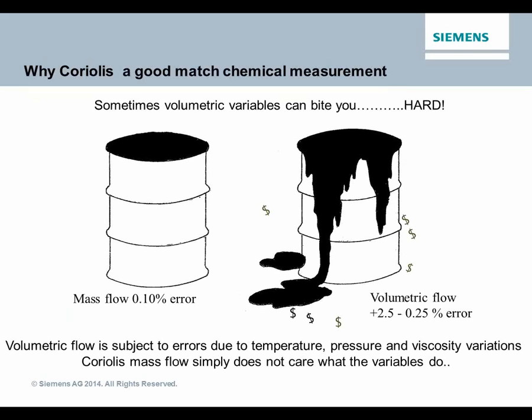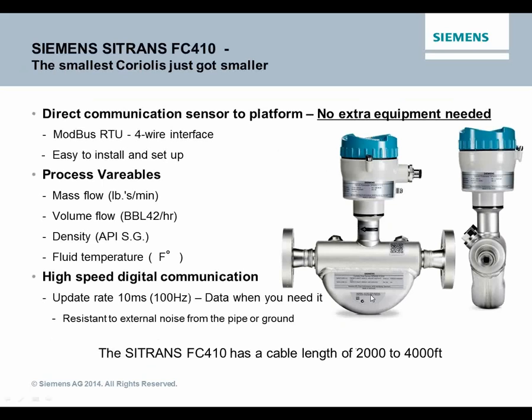And the reason mass flow is important is all the reasons I mentioned before, is that you don't need any changes, any adjustments, any corrections. But if you're measuring a fluid, such as oil in this particular example, if you fill this barrel up to the very brim in the morning in a southern Texas oil field and you don't put a lid on it, by the time afternoon comes along and the temperature's gone from 40 degrees F to 105, you're going to have spillage because you have expansion of the fluid. Mass is not affected by this, and that is one of the key benefits of Coriolis.